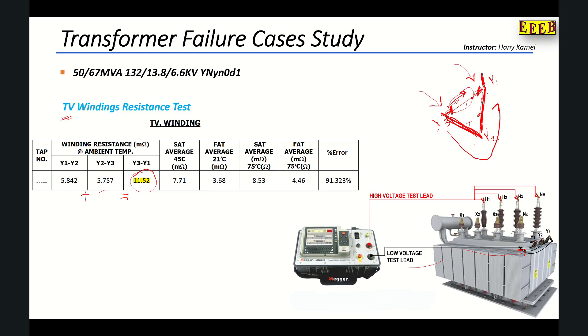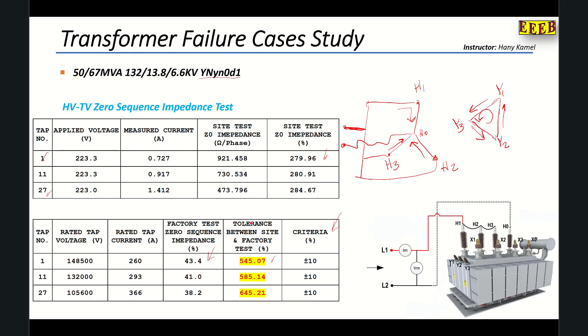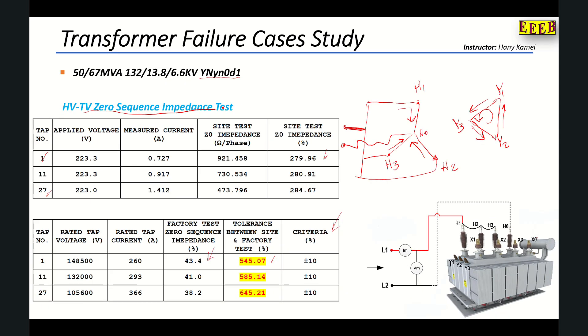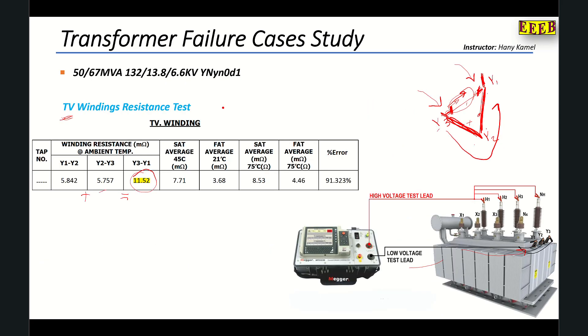This open branch is why the zero sequence and positive sequence impedance tests both failed. After draining the transformer oil and performing an internal inspection, we found a problem in that branch. The manufacturer reconnected the winding and the results were perfect.